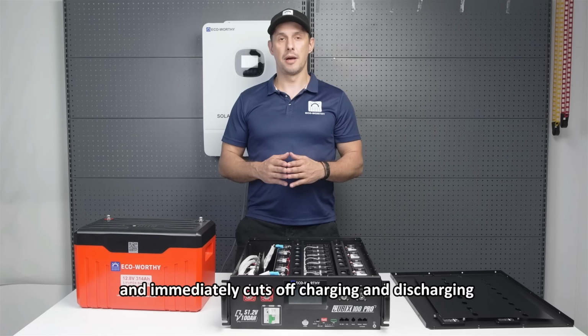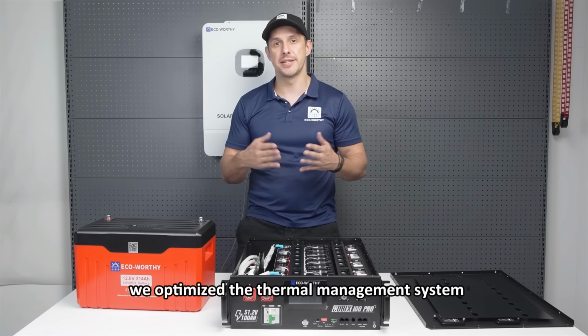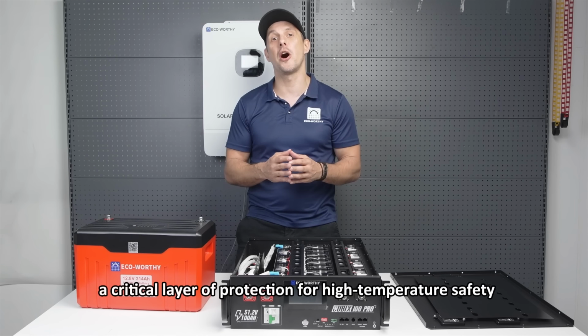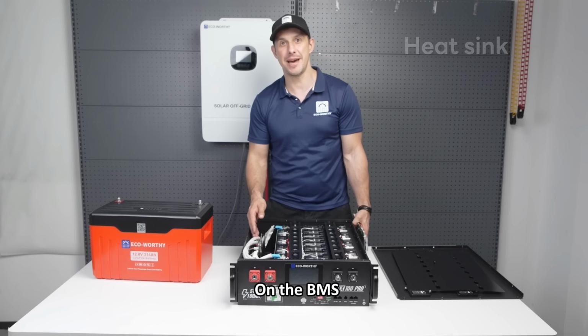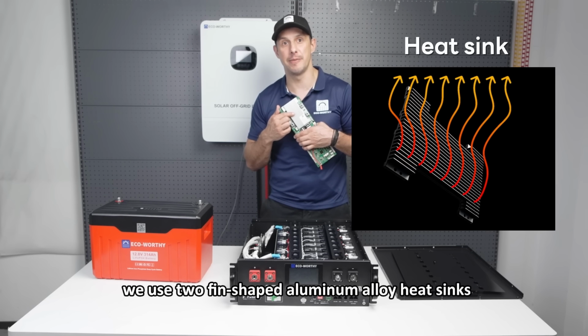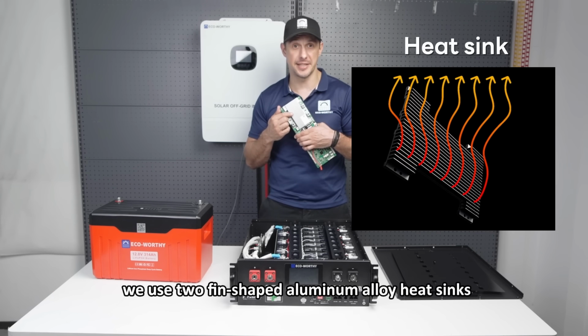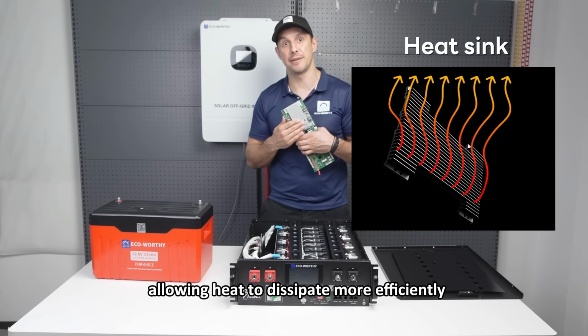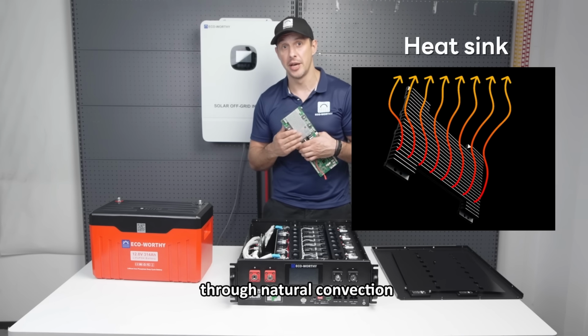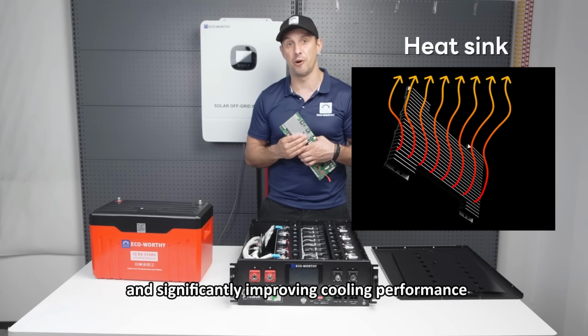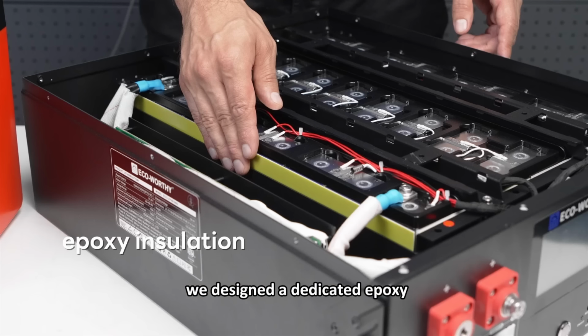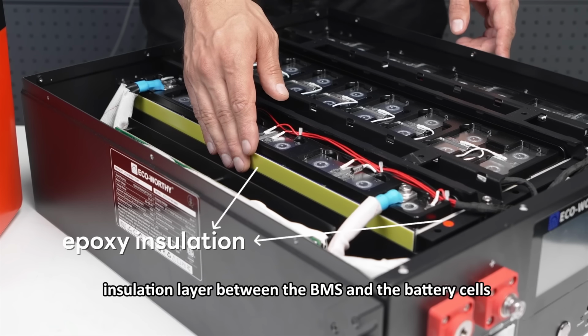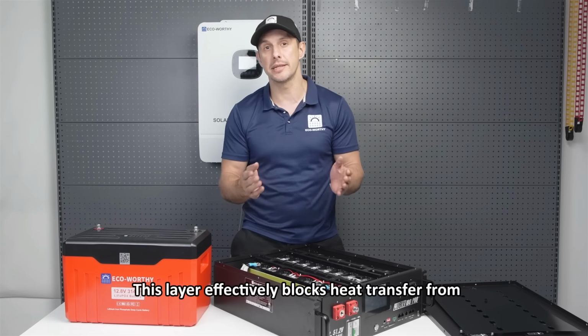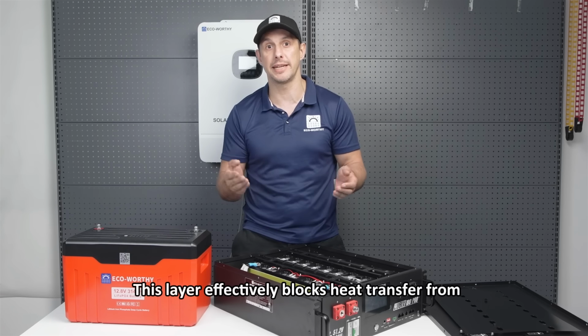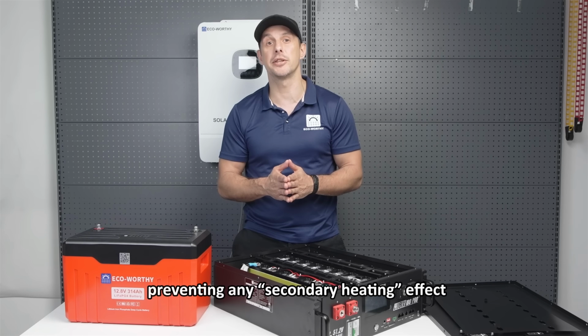Finally, we optimize the thermal management system, a critical layer of protection for high temperature safety. On the BMS, we use two fin-shaped aluminum alloy heat sinks mounted vertically. This alignment keeps the fin in the same direction as airflow, allowing heat to dissipate more efficiently through natural convection and significantly improving cooling performance. At the same time, we designed a dedicated epoxy insulation layer between the BMS and the battery cells. This layer effectively blocks heat transfer from the heatsink to the cells, preventing any secondary heating effect.